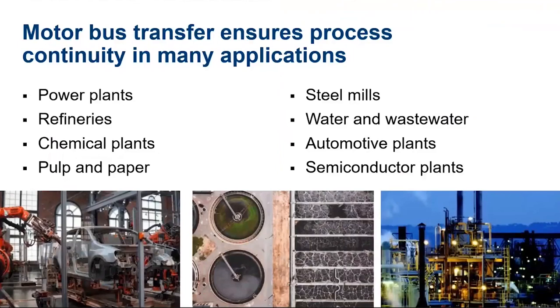Any industry where continuous process is essential, we need motor bus transfer. Reliable service is key to critical facilities to provide continuous process, avoid costly unplanned shutdowns, and above all, personnel safety. If an outage occurs, the typical cost of an outage could be $50,000. Depending on the size of the system, it can also go many times higher. The slide here shows examples of industries that need motor bus transfer. But the applicable industries are certainly not limited to just these industries.